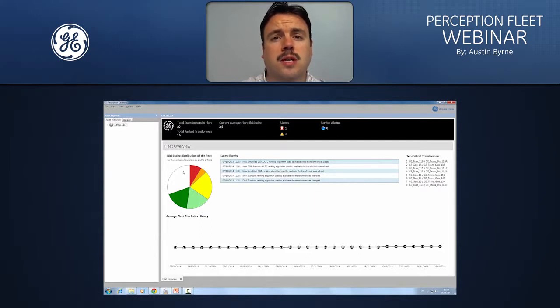That could either be because the user or the organization has chosen not to evaluate those transformers, or there is no measurement information to evaluate for those assets. Under the latest events section, we display every event that has been captured by Perception, whether that's shifting of assets within the fleet ranking table, a change in risk index for an asset, or an asset triggering an alarm. So if a multi-gas monitor, for example, experiences a high alarm, or a service alarm, if for whatever reason you're unable to communicate with the online monitor, any event that's captured in Perception is output to this single display. It means it's very easy to see exactly what's happening within the fleet without having to drill down into the asset tree to look at individual items.